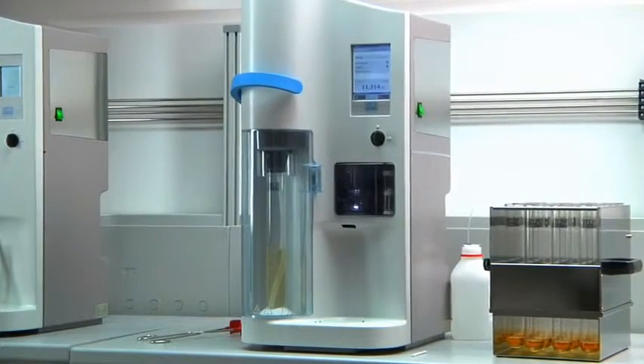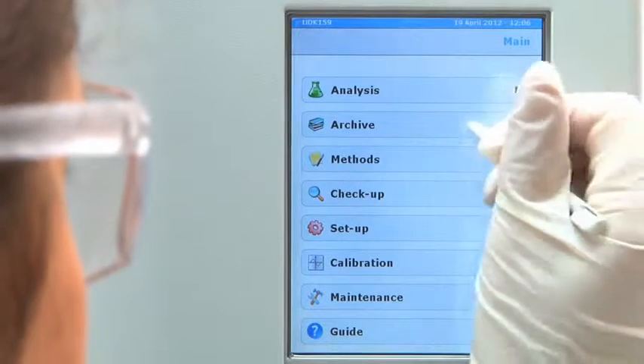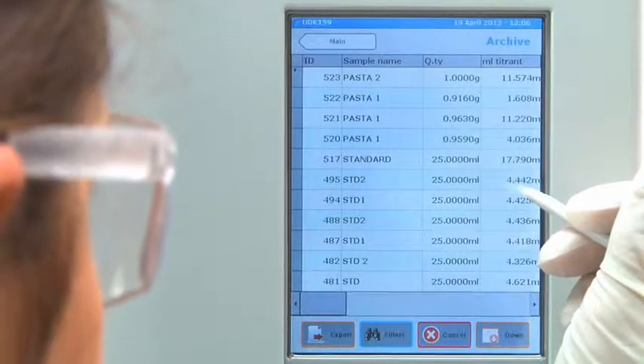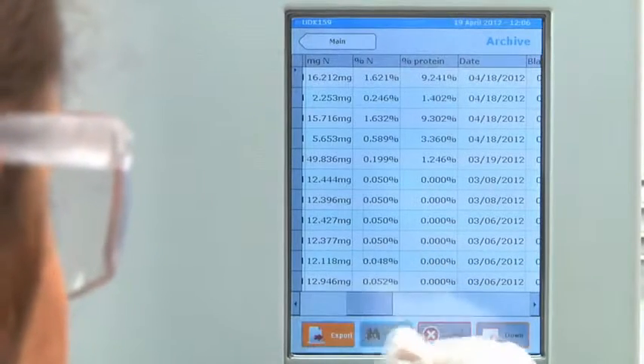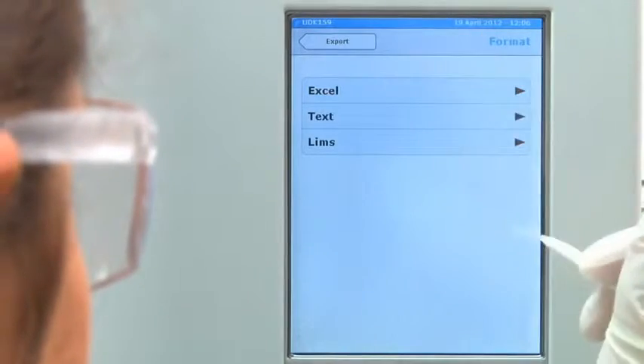Operator safety, time saving and reduction of manual activities are improved by automatic tube draining of hot distillation and titration residues. Following distillation and titration, the display presents all the results, which are stored on the onboard archive for enhanced traceability and improved operation in accordance with GLP. The data can be managed remotely via Ethernet or exported to a USB pen drive.